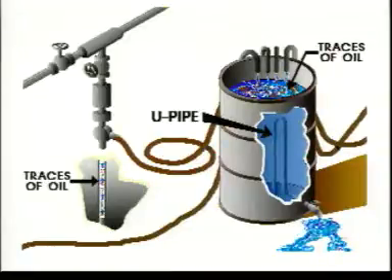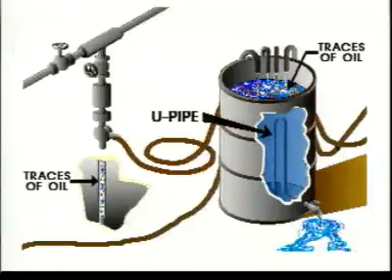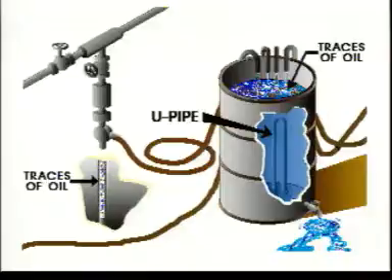If there is oil in the water, the coil may be leaking. The coil must be closed and sealed, then tested and repaired at a suitable time. Oil must not be allowed to return to the boiler.